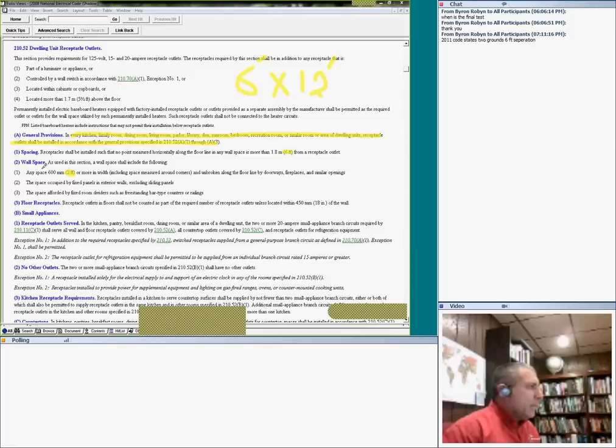Okay, all these bases guys have to have, if it's 2 feet or more, you have to provide a receptacle. Floor receptacles: if you install a floor receptacle, because you can put them in the wall, receptacles installed in the floor shall not be counted as part of the required receptacles unless they are within 18 inches of the wall. So can you put a receptacle in the floor? No problem, bring it on. As long as it's within 18 inches, it will count as a wall receptacle.